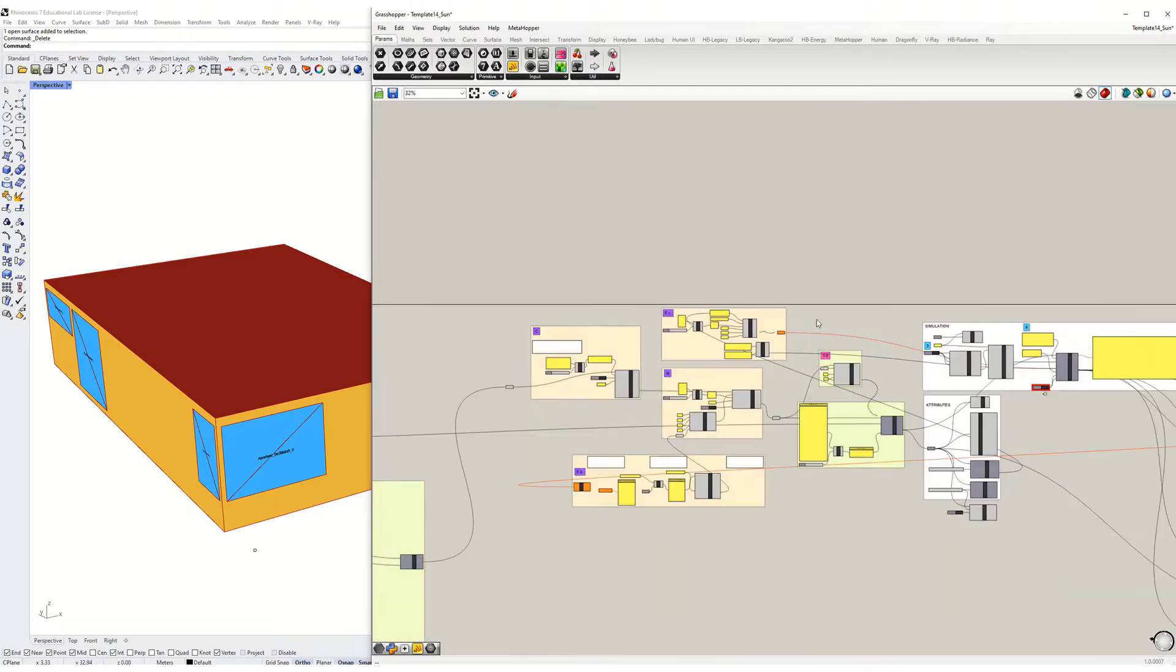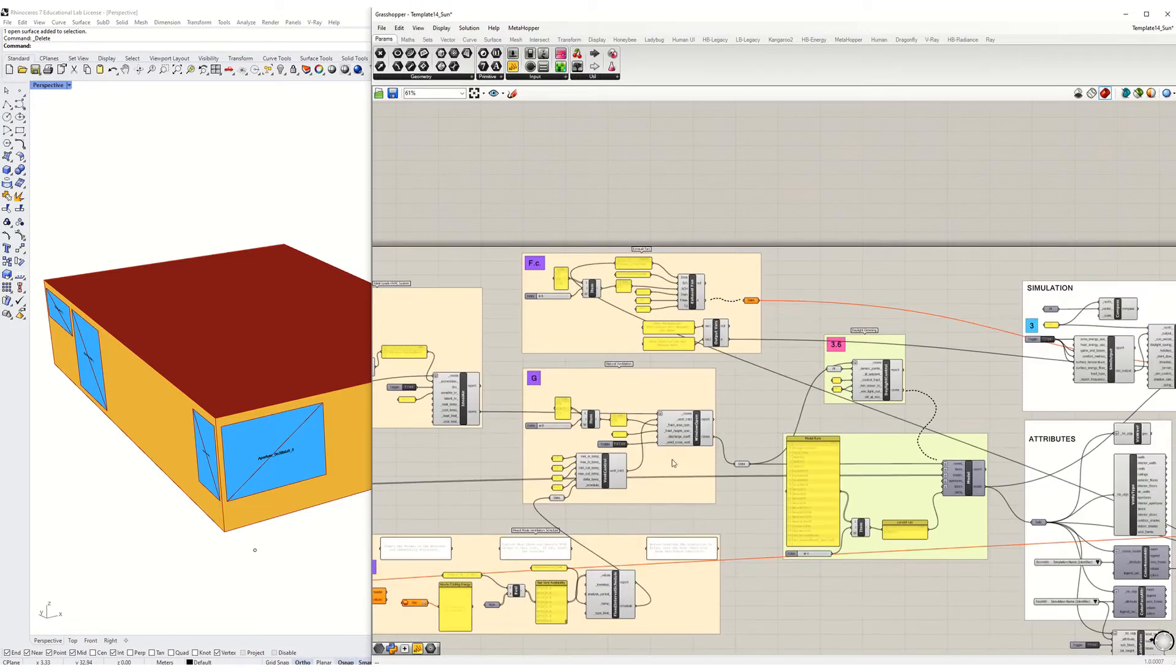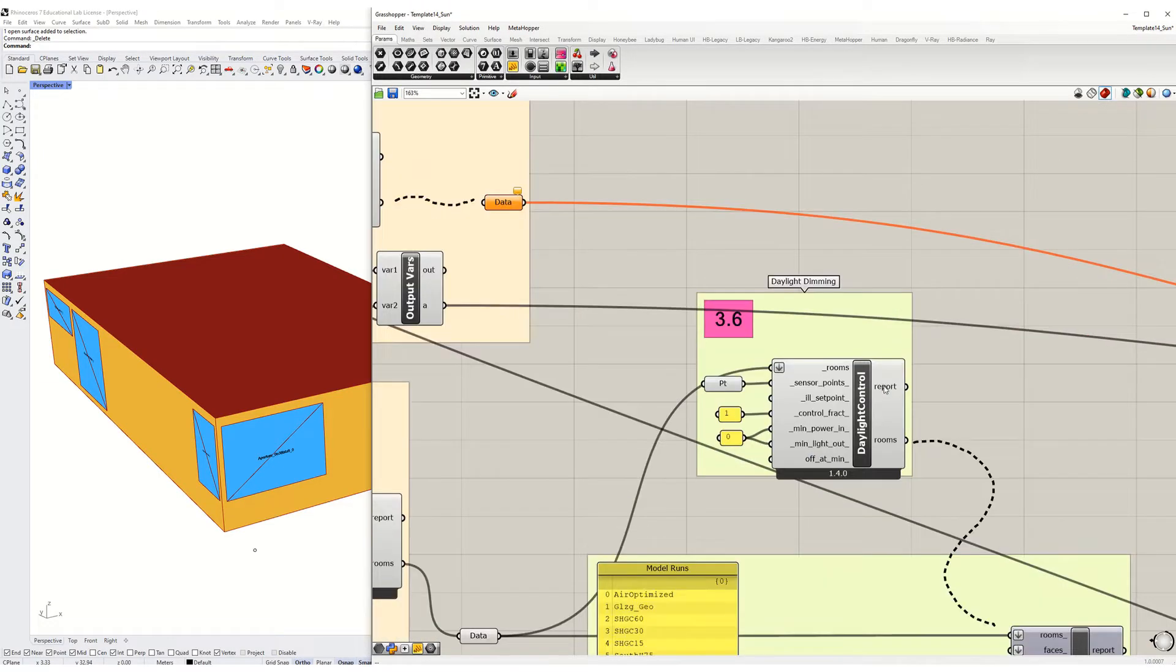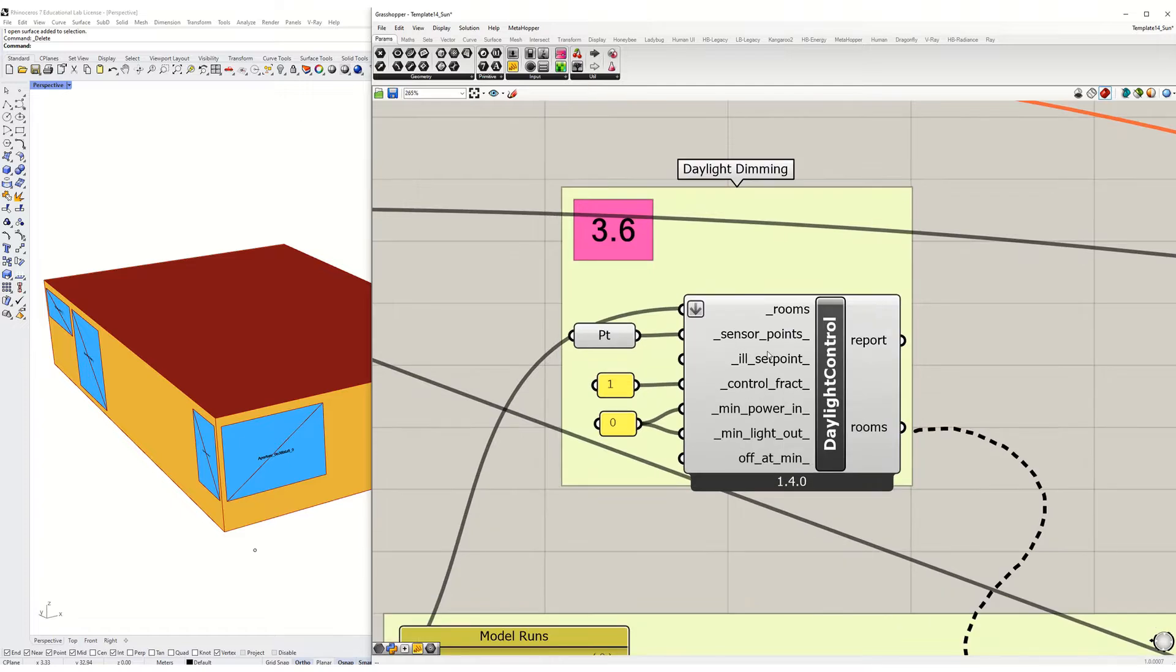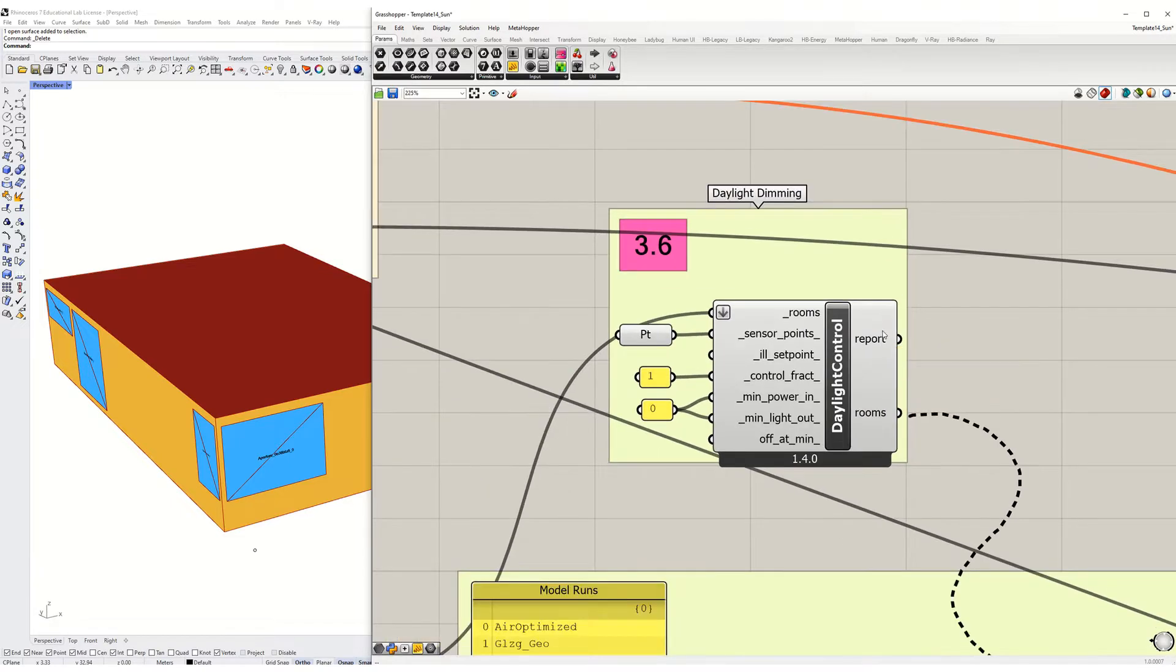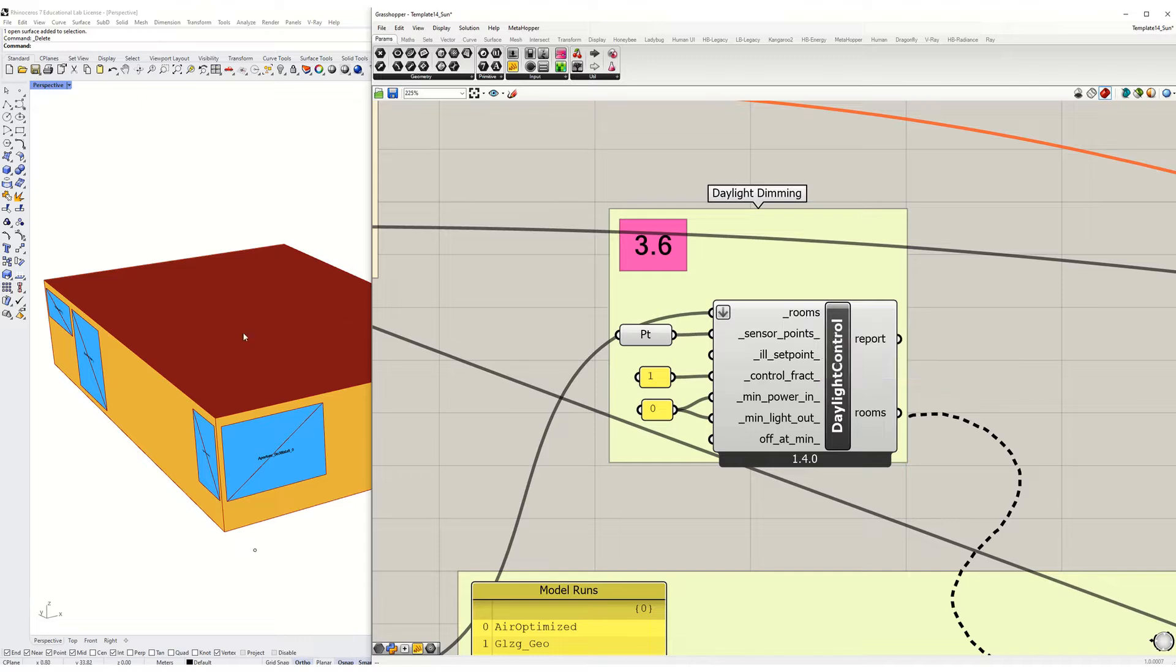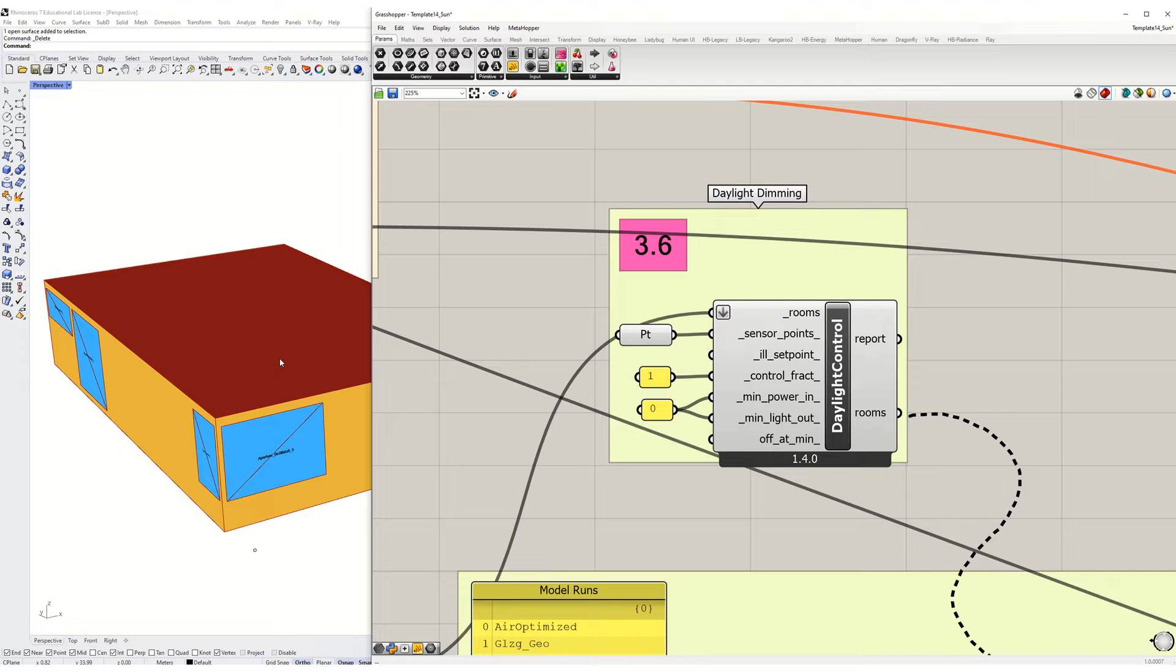The daylighting component in this is 3.6 and the way it works is that there'd be a sensor inside the zone and depending on how much illuminance is on that sensor, it will dim the electric lights accordingly. So you should see a fair amount of electric light savings depending on how much glazing you have and where the sensor is located.